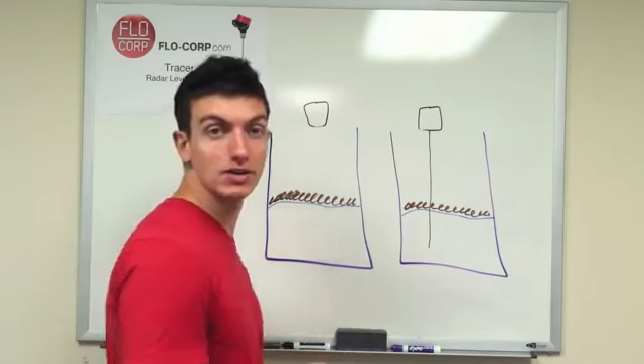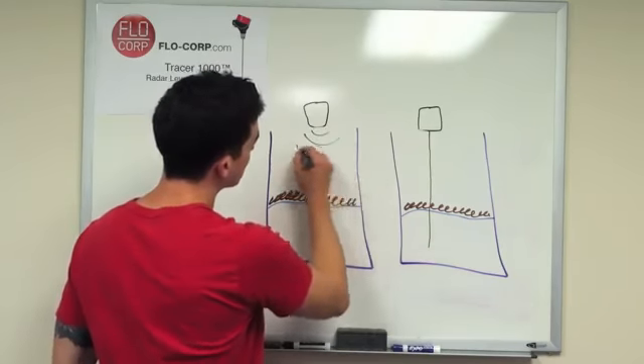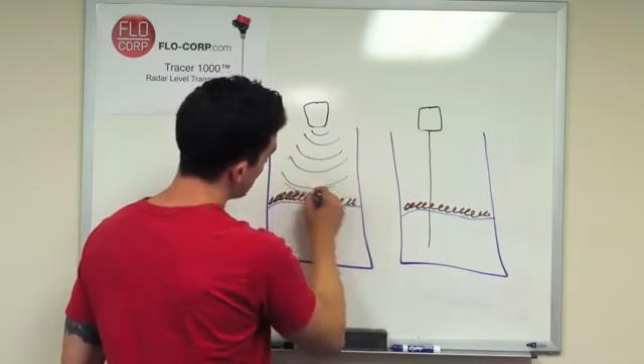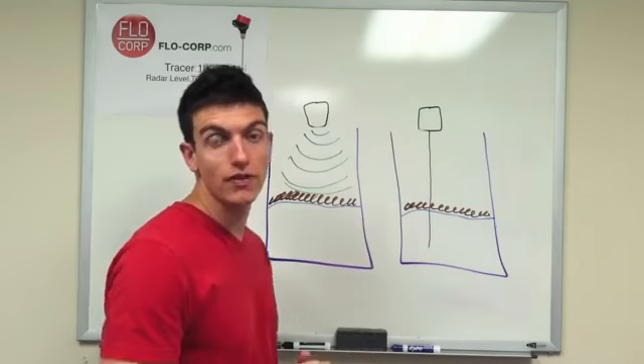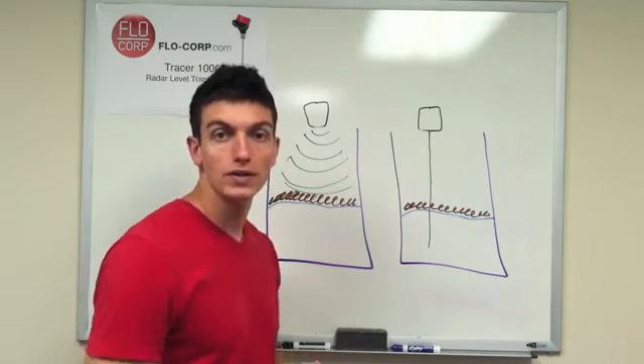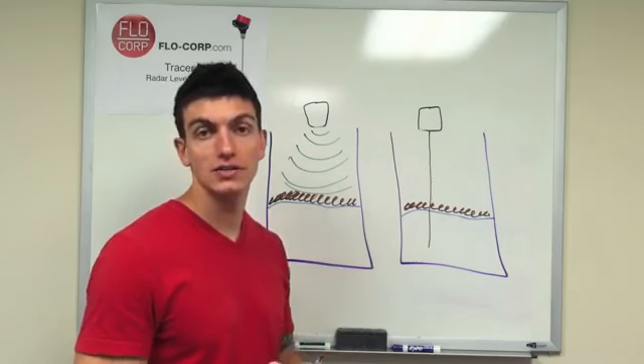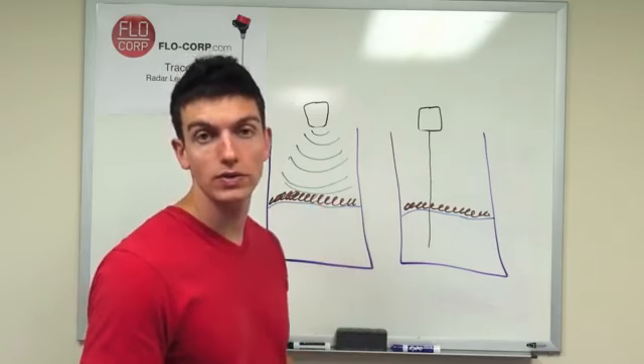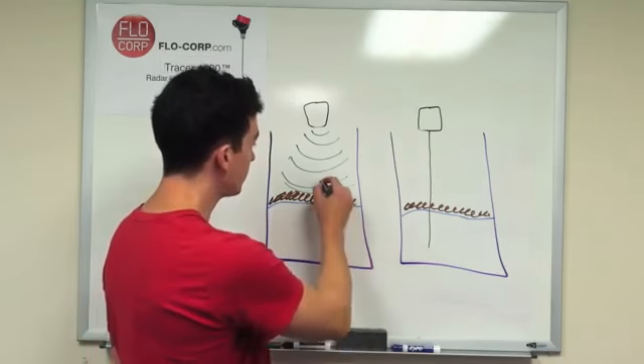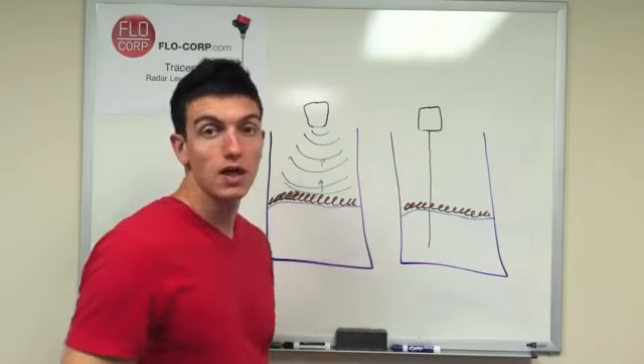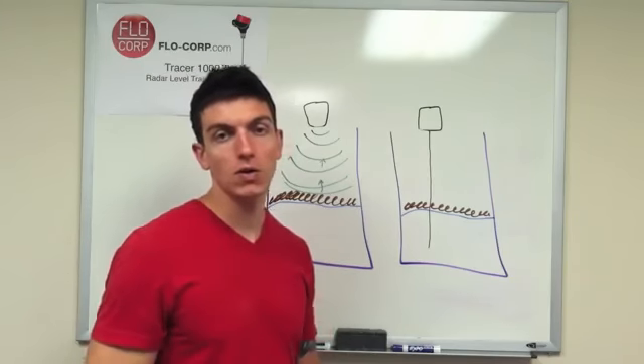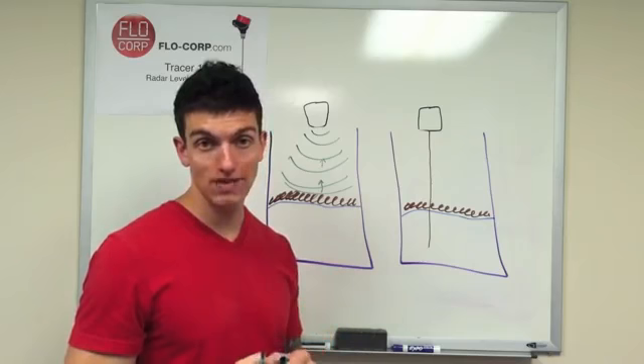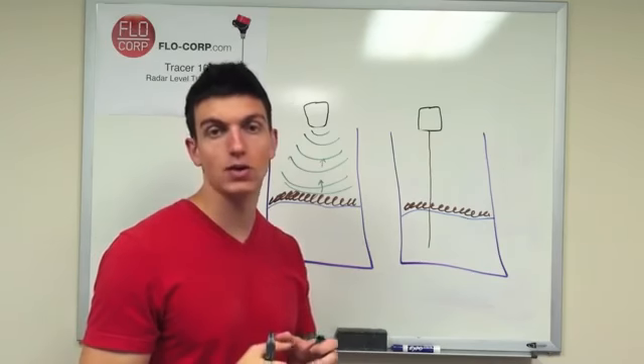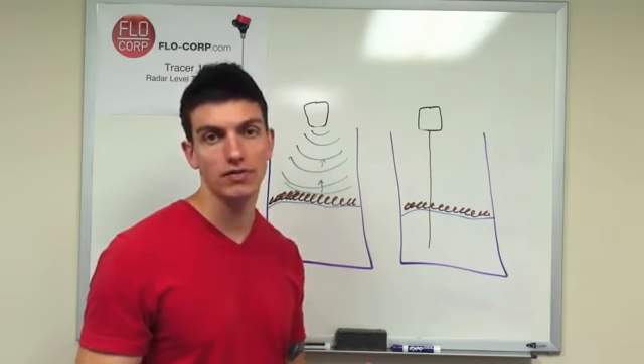The ultrasonic meter sends a signal, and when it hits the surface of the foam, the problem with ultrasonic sound energy is that it's absorbed by foam. So most of the signal will disappear here. We'll probably get a small return of some sort. So that may take a level measurement, or the ultrasonic transducer may factor it out and reason that the signal wasn't strong enough, so it must not be the actual level of this liquid we're trying to measure.